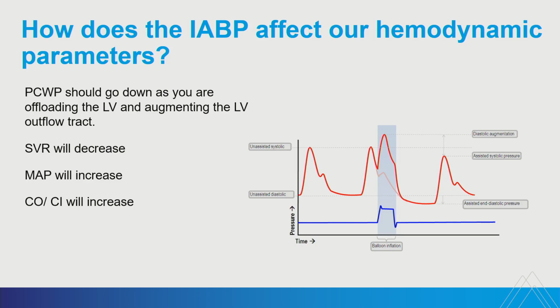So you have a balloon with fiber optic, obtaining a beautiful tracing. You have a transducer hooked up to this flush line that you're not using. Most hospitals will take that transduced signal and bring it directly to the bedside monitor like you would a radial A-line. So you have 2 A-lines, one going to the bedside monitor, one coming from the pump. One of the very common questions we get is the balloon pump is reading systolic 100 over 50, but the bedside monitor is reading systolic 160 over 50. What's wrong? Well, your other monitors do not understand that that high is not systoling. That's a peak pressure during diastole.